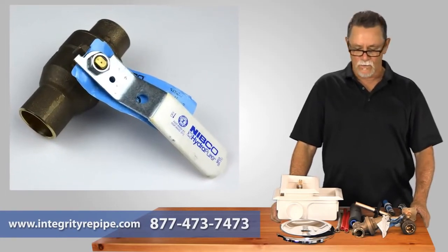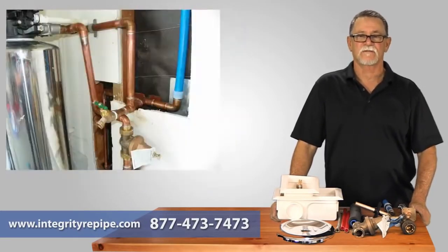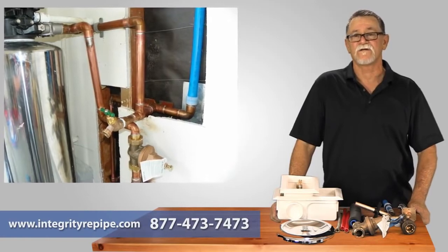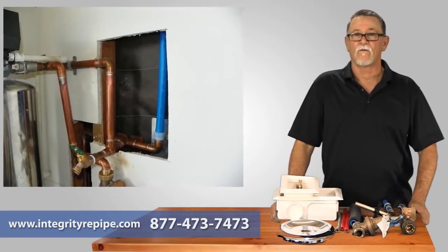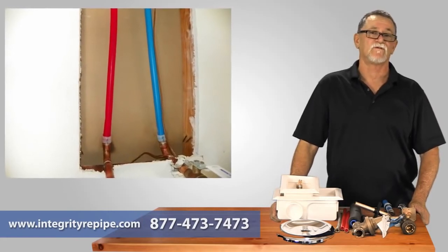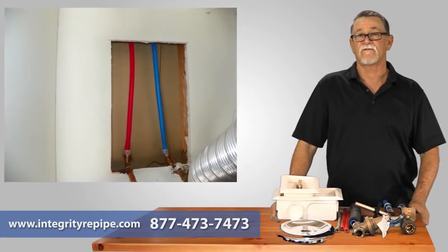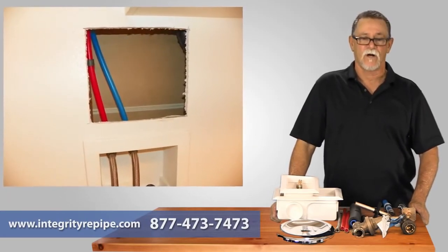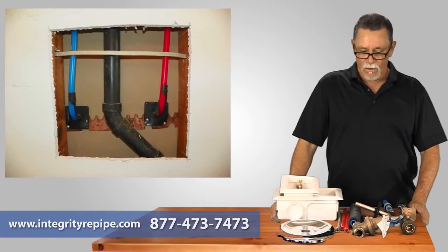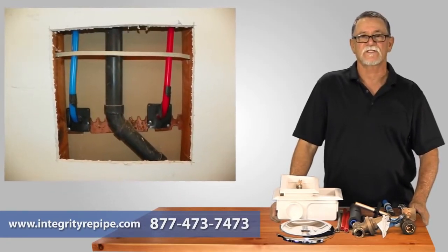So we don't do the manifold systems, and we don't do the home run systems, because a home run system will give you less than 50% of the gallons per minute. A remote manifold system will give you 3/4 of the gallons per minute possible. A modified branch system will give you the most gallons per minute that is humanly possible. So I'm always going to recommend a PEX system over a copper system.